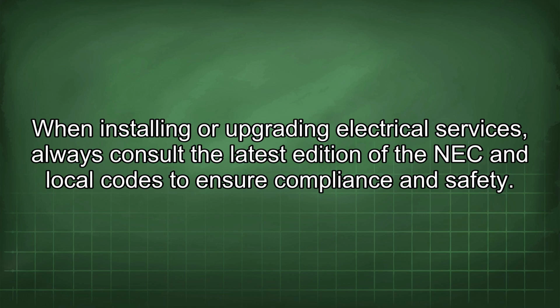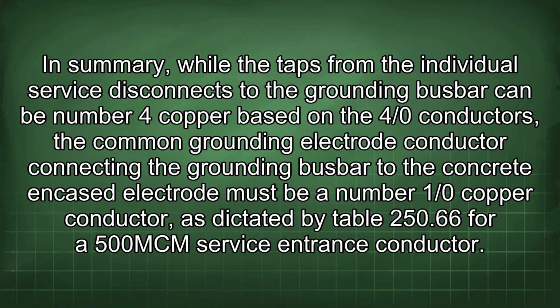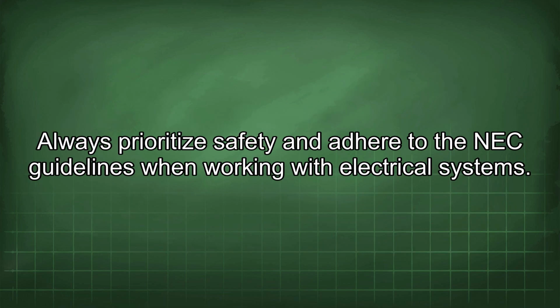In summary, while the taps from the individual service disconnects to the grounding busbar can be number 4 copper based on the 4/0 conductors, the common grounding electrode conductor connecting the grounding busbar to the concrete encased electrode must be a number 1/0 copper conductor as dictated by table 250.66 for a 500MCM service entrance conductor. Always prioritize safety and adhere to the NEC guidelines when working with electrical systems.